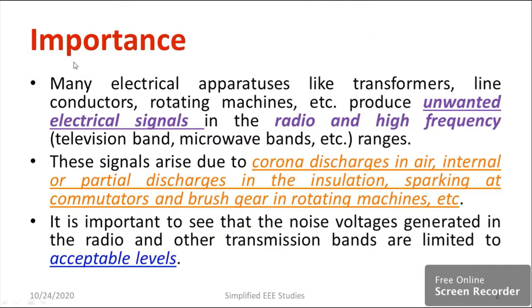First and foremost, I would like to discuss the importance of measurement of radio interference. Many electrical appliances like transformers, line conductors, and rotating machines produce unwanted electrical signals in the range of radio and high frequency — for example, television band, microwave, and more than megahertz. These signals will directly interact with the communication channel and distract the signal passing through it. These signals are produced due to corona discharges in air, internal or partial discharges in the insulation, and sparking at commutators and brush gear in rotating machines.